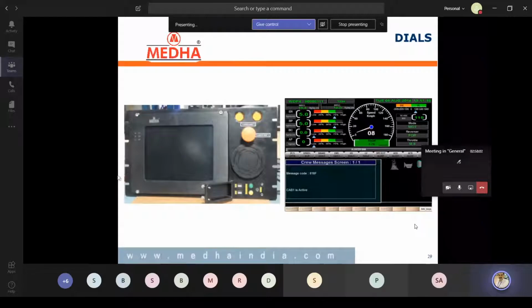And on the front fascia here we can find 3 LEDs, L1, L2, L3. These 3 LEDs are provided to know the functionality of the display units. And all these 3 LEDs are bicolor LEDs. For normal operation, the L2 LED should glow in red color. L2 in red color means the display is healthy and working fine. In case the internal temperature rises and it goes into safe shutdown mode, then the L2 LED becomes yellow, instead of red.